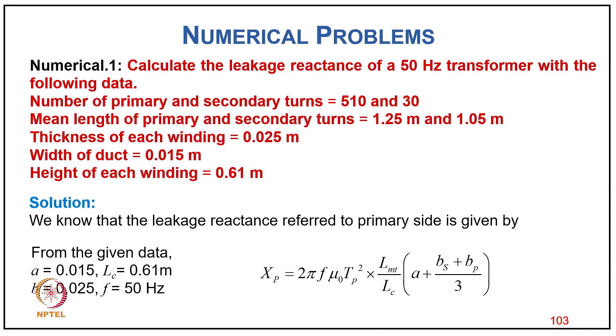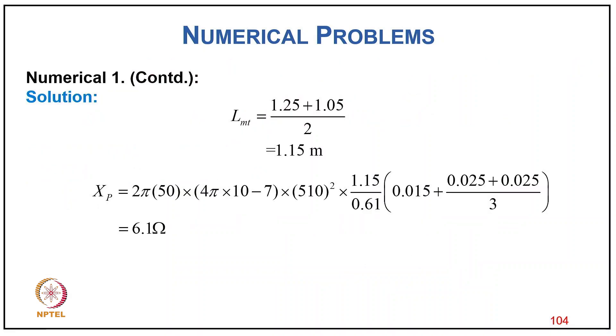Numerical problem 1: Find the leakage reactance of a transformer with: primary/secondary turns 510/30, mean turn length of primary/secondary 1.25 m, thickness of each winding 0.025 m, width of duct 0.015 m, height of each winding 0.61 m. Using Xp = 2πf×μ₀×Tp²×LMT/Lc × [a + bp/3], with LMT = (1.25+1.05)/2 = 1.15 m, the result is Xp = 6.1 Ω.